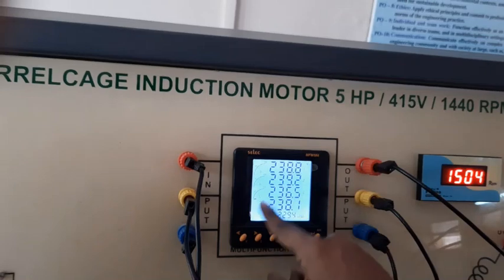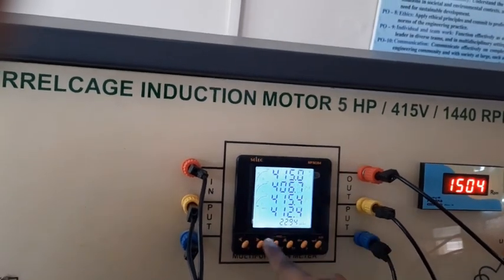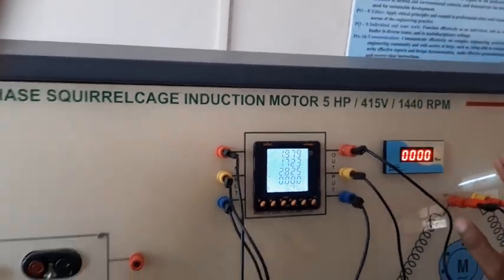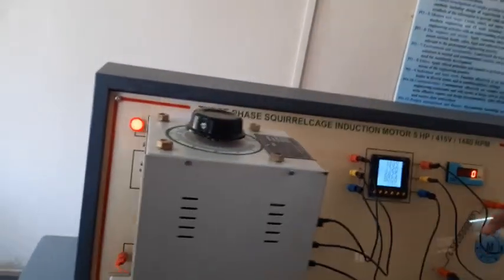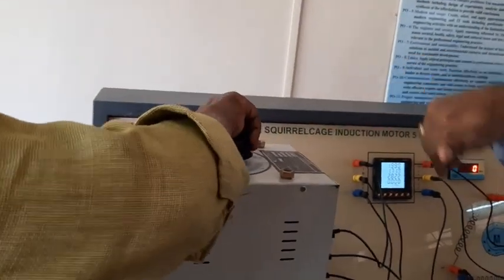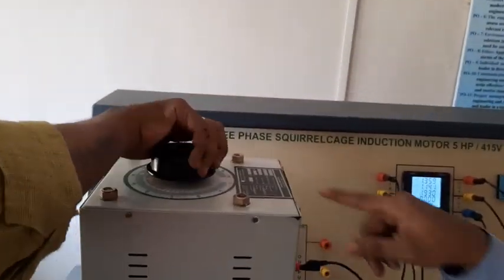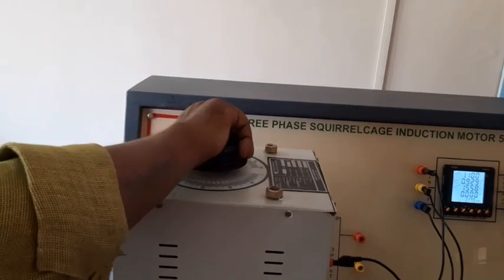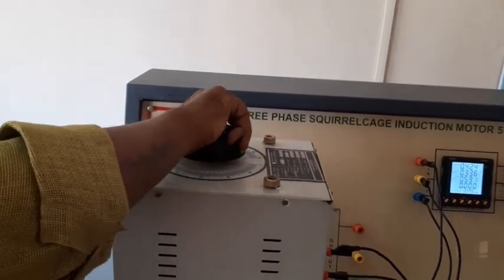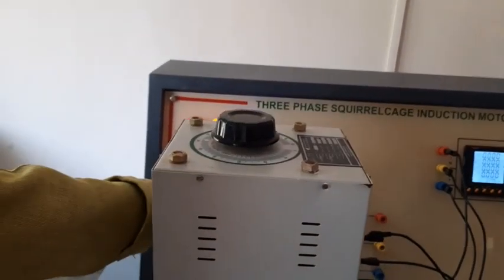This is the no load voltage. No load voltage is 415 volt. No load current is 1.9 ampere. So this is the no load reading test of the induction motor. Now switch off the supply. Slowly come down to the zero position of the auto transformer. Switch off the supply.